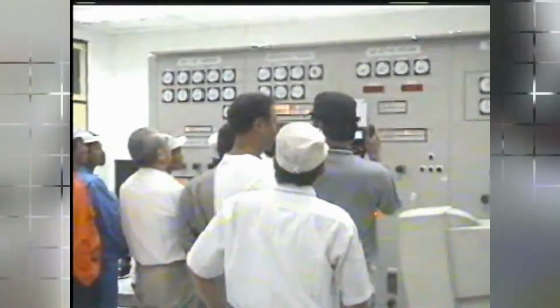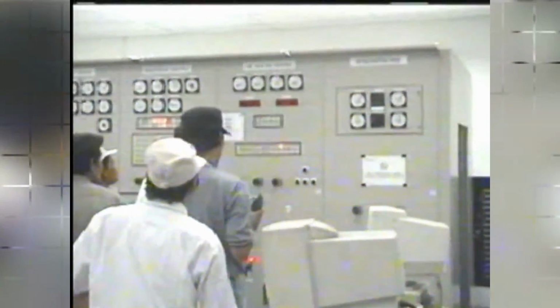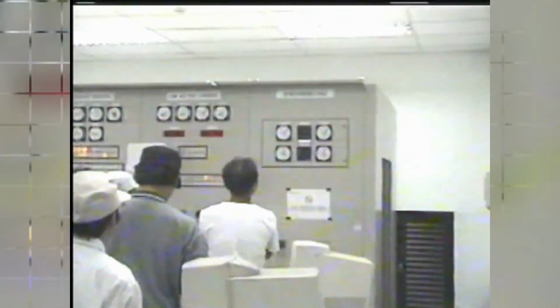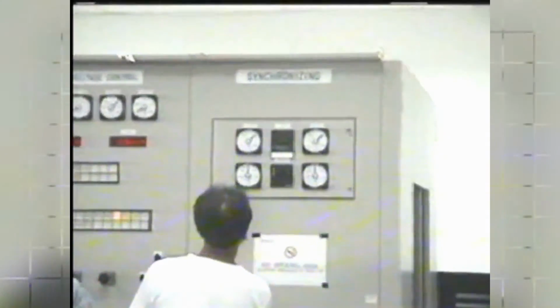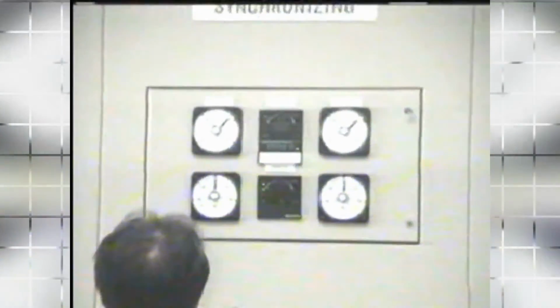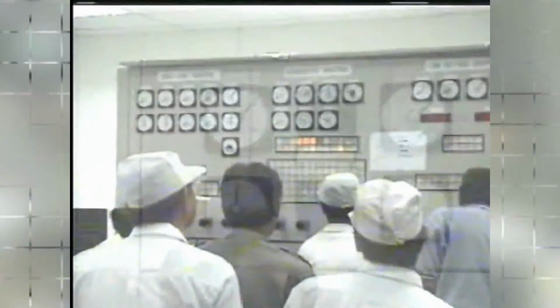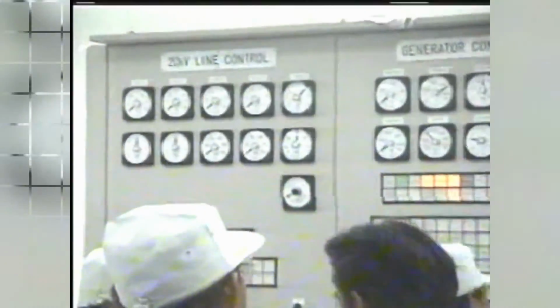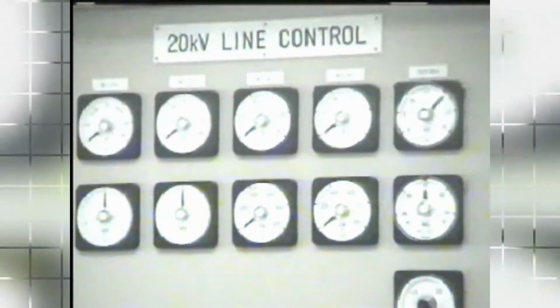Following the stationary functional test and watering into the turbine and waterway, the rotational test shall demonstrate that the works are properly installed, fully operational, free from vibration and leakage, correctly adjusted, and that the performance guarantees are met. It is necessary to cooperate on works for watering and dewatering of the turbine and waterway and carry out the water tightness test for the machinery.